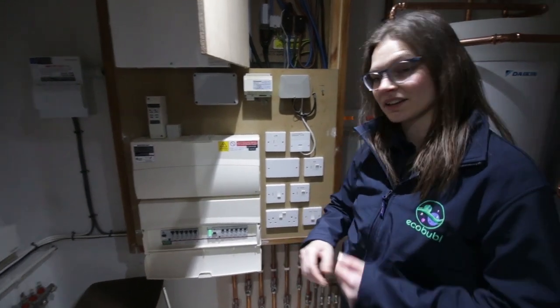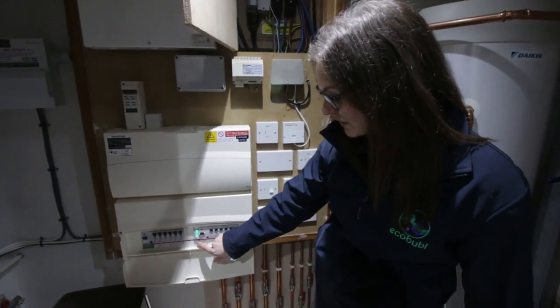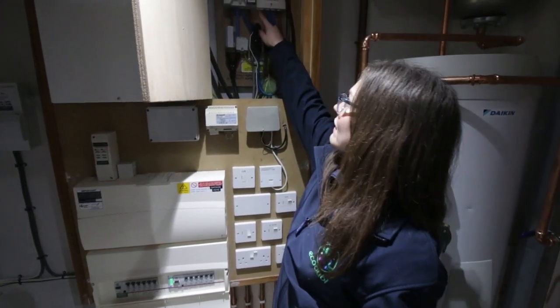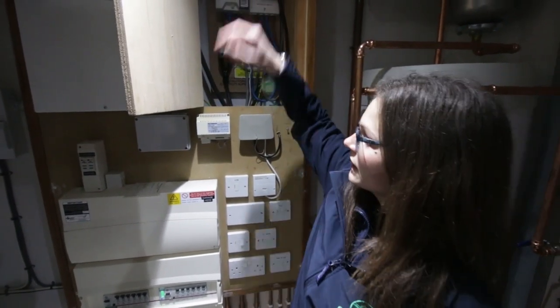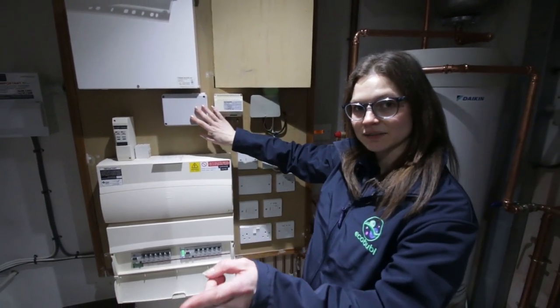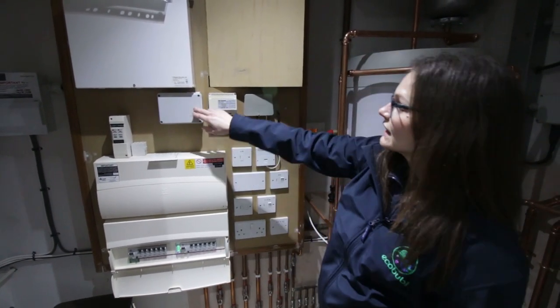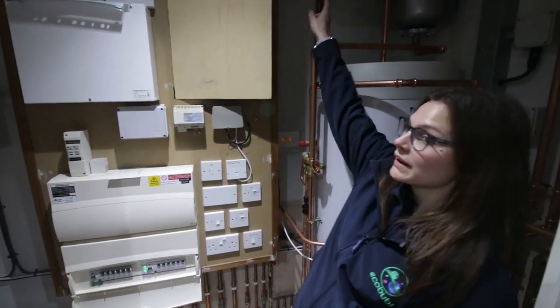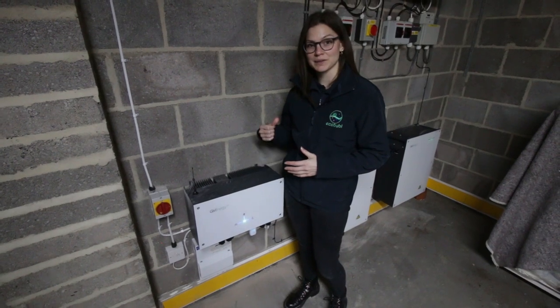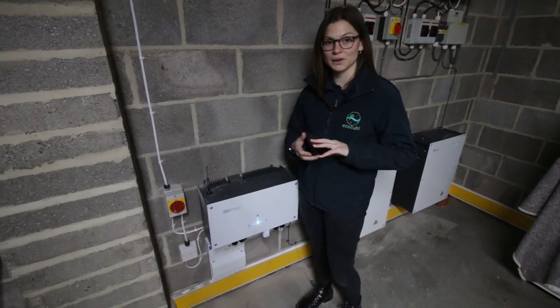So we're down at the meter end, inside the house now, and we've got our EM115 installed just here. That's connected up to our CT clamp with the arrow facing the consumer units. The LoRa is installed in this white box here and that's what's sending the signal down to the AC couple inverter — the antenna for that is just located up here. Let's take a look at the drawings for LoRa and how the AC couple inverter, battery pack, and existing PV system all work together.